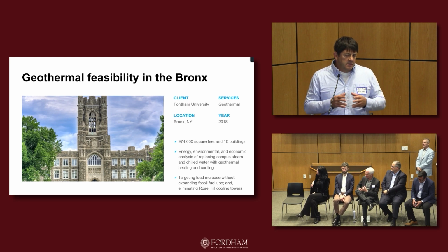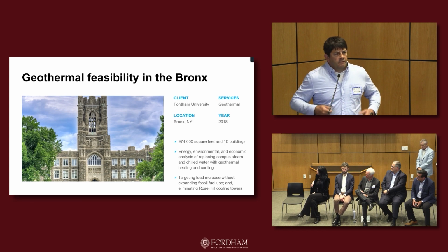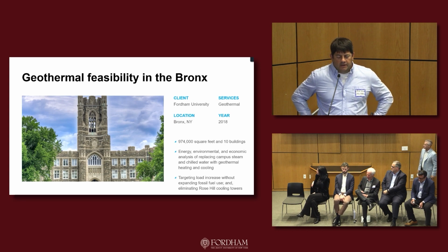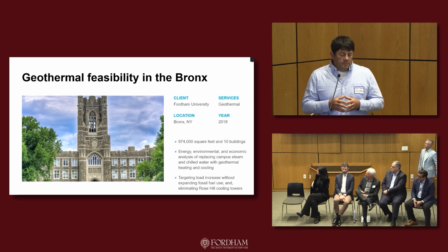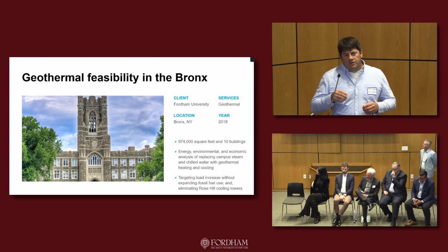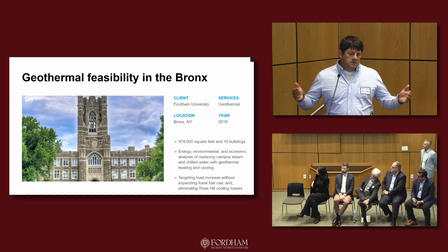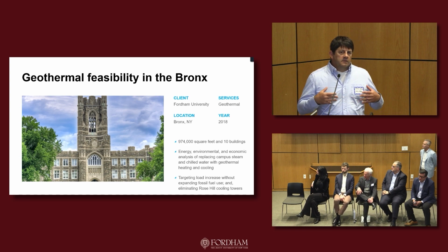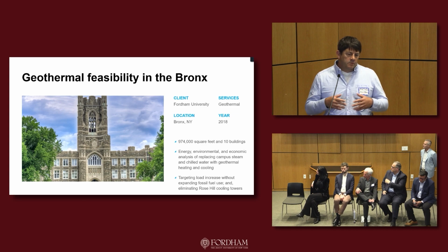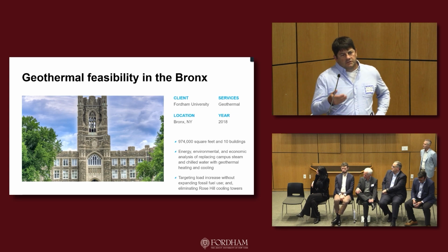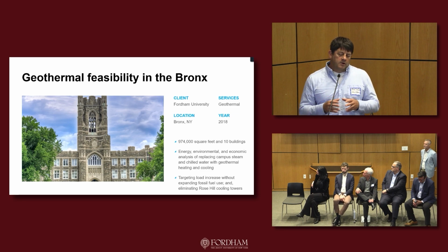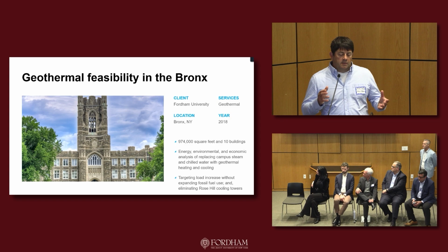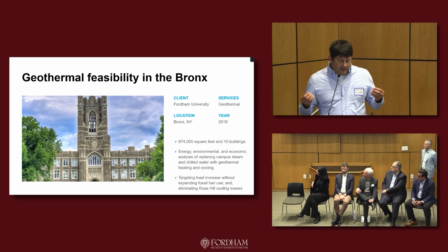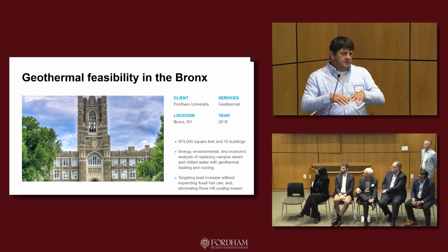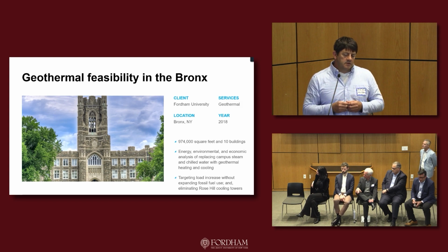What we're looking at, which is traditional for our company, is we typically convert academic campuses—not industrial or pharmaceutical—at about 130 degrees. The reason we do 130 is when you have a lot of residential living, we'll do instantaneous water heating for all the domestic water, using a couple of double plate frame heat exchangers. It's a nice way to pick up 100% of that domestic water. But also we can move our energy around as students leave the residence halls and go to academic buildings, so our equipment doesn't have to be sized for that peak load. It's actually a well-diversified load where we can really downsize our equipment.